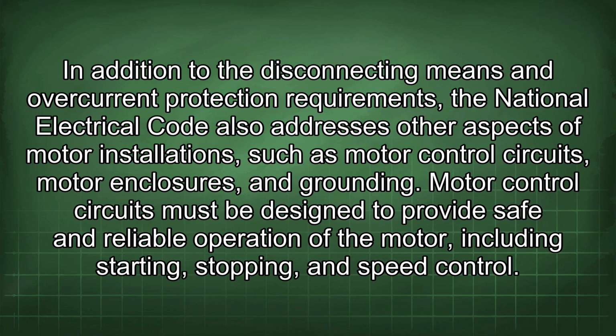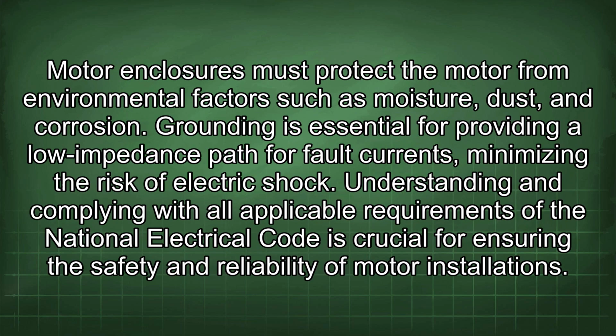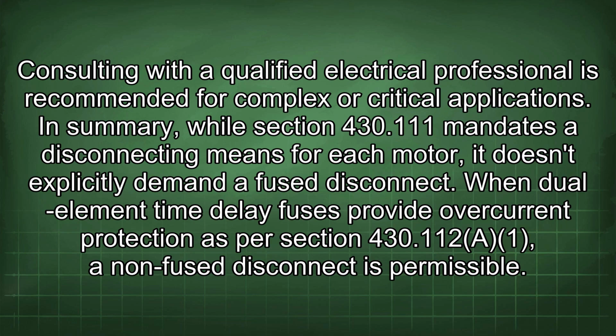In addition to the disconnecting means and overcurrent protection requirements, the National Electrical Code also addresses other aspects of motor installations such as motor control circuits, motor enclosures, and grounding. Motor control circuits must be designed to provide safe and reliable operation of the motor, including starting, stopping, and speed control. Motor enclosures must protect the motor from environmental factors such as moisture, dust, and corrosion. Grounding is essential for providing a low impedance path for fault currents, minimizing the risk of electric shock. Understanding and complying with all applicable requirements of the National Electrical Code is crucial for ensuring the safety and reliability of motor installations. Consulting with a qualified electrical professional is recommended for complex or critical applications.